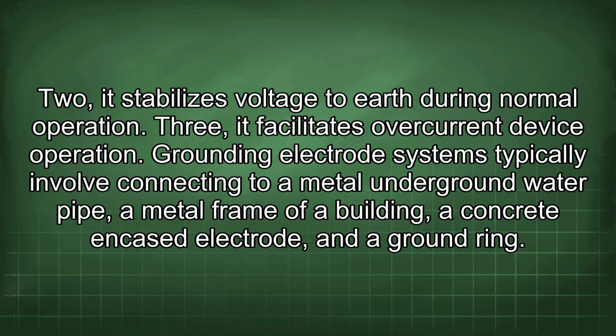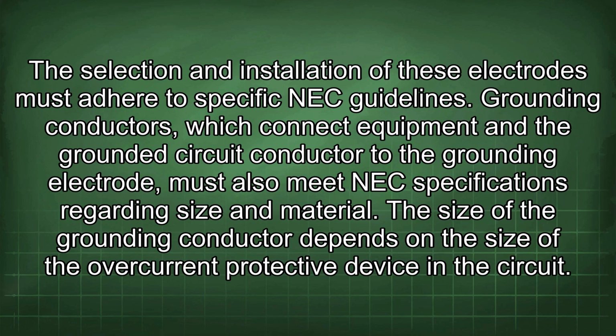Grounding electrode systems typically involve connecting to a metal underground water pipe, a metal frame of a building, a concrete encased electrode, and a ground ring. The selection and installation of these electrodes must adhere to specific NEC guidelines.